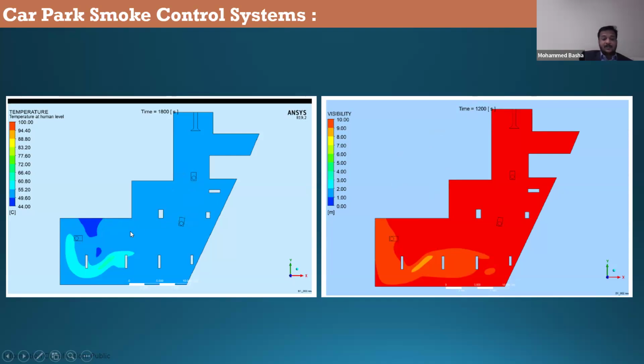Now, one more important thing is that a jet fan works based on thrust. There is no flow rate taken as accountable because it's a thrust. It pushes the air from here, pushes here, pushes here. But this is the extract, right? So I'm still seeing they are designing this extract for 10 air changes. It's a more conservative approach, but I would say this is a very high value.